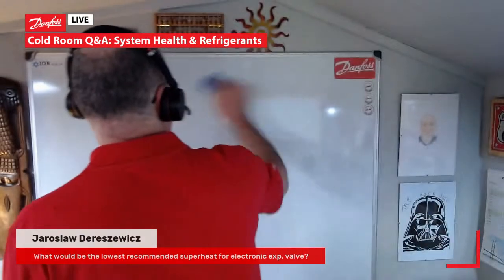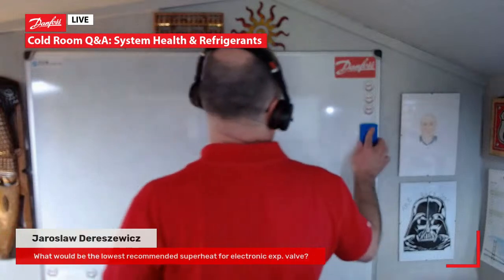Okay, another question's come in. So what would be the lowest recommended superheat for an electronic expansion valve? Yeah, that's a good question. Let's come back to that capillary tube one. That's an interesting one. I'm going to look at that later on. I would say for an electronic expansion valve, you don't want to go any lower than 5 or 6 Kelvin. That to me is plenty low enough.